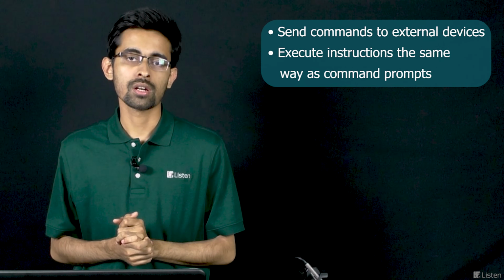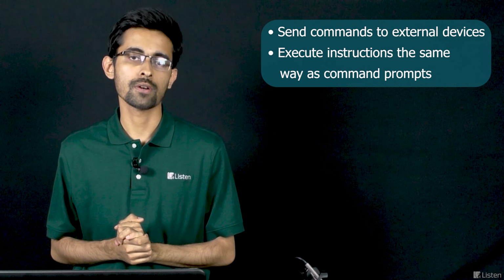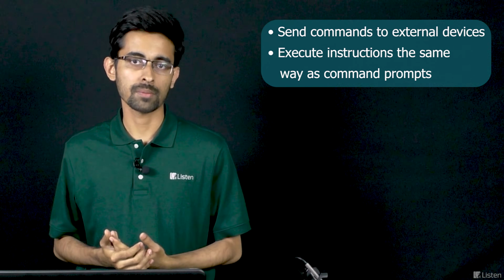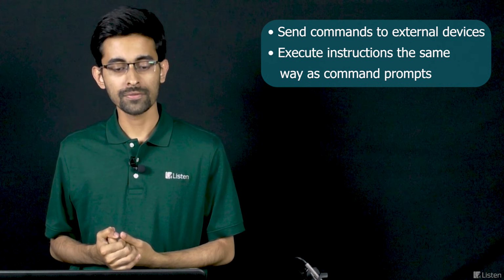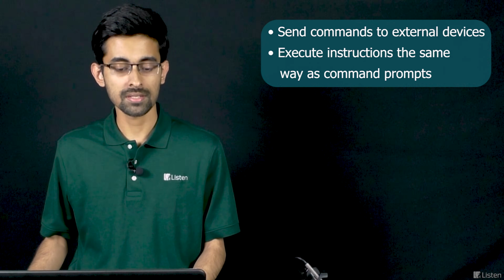Alright, so what I'm going to show you right now is how you can make use of custom steps inside a sequence to send commands to an external device, for example, an Android phone. SoundCheck has these step templates called custom steps, which you can make use of, similar to the other step templates that we provide, and one of them is named the system custom step.